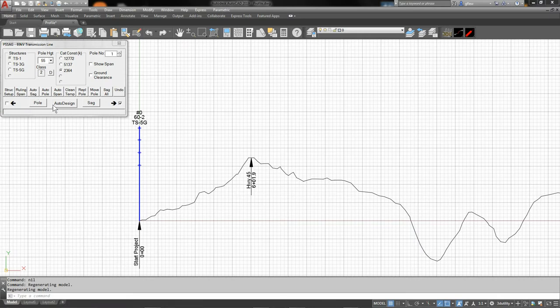So to begin our design, what we want to do is emulate what I did for many years with the old plastic sag curve, is find the point at which the ground clearance just clears the ground, and then we can from there spot our pole.